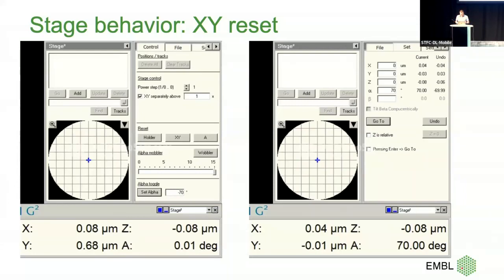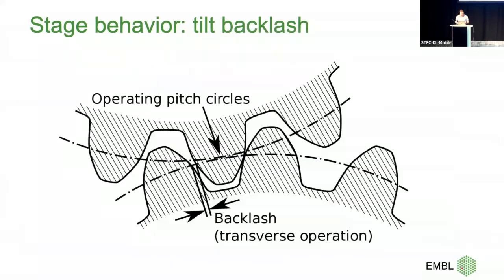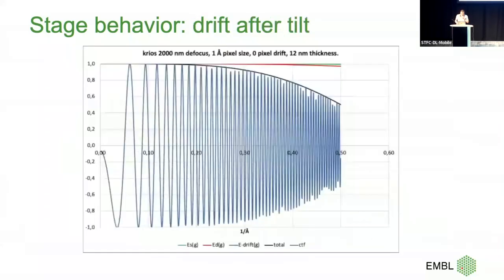Another important thing is tilt accuracy. I asked ThermoScientific and we actually tested this with Luca using a silicon sample with convergent beam electron diffraction, getting a Kikuchi pattern — very sensitive to stage tilt. It was very, very accurate. That's why I say you should in principle not need to solve for stage tilt. There is backlash on the stage when you reverse direction, so the original script always tilted in one direction: on the minus side you overshoot three degrees and come back from the same direction.